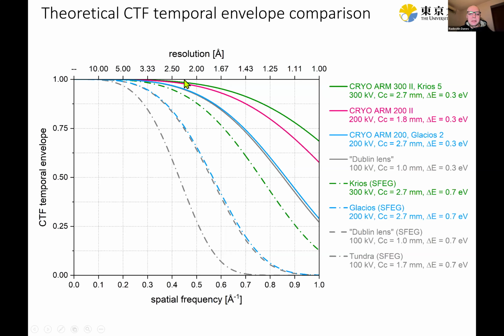I haven't put the curve here, but my guess is that it will be even higher than the green line here. Then the CryoARM 200 version 2, which I'm presenting about here, is the purple line, so it comes in second. Then we have the Thermo Fisher Glacios 2 here, the blue line. Then comes the traditional Krios with the Schottky FEG, here the dashed green line, and other Schottky FEG machines. So you see here the cold field emission gun provides a big boost in the overall optical performance on its own. Of course, when combined with the narrow gap objective lens pole piece, you see it gives another push.